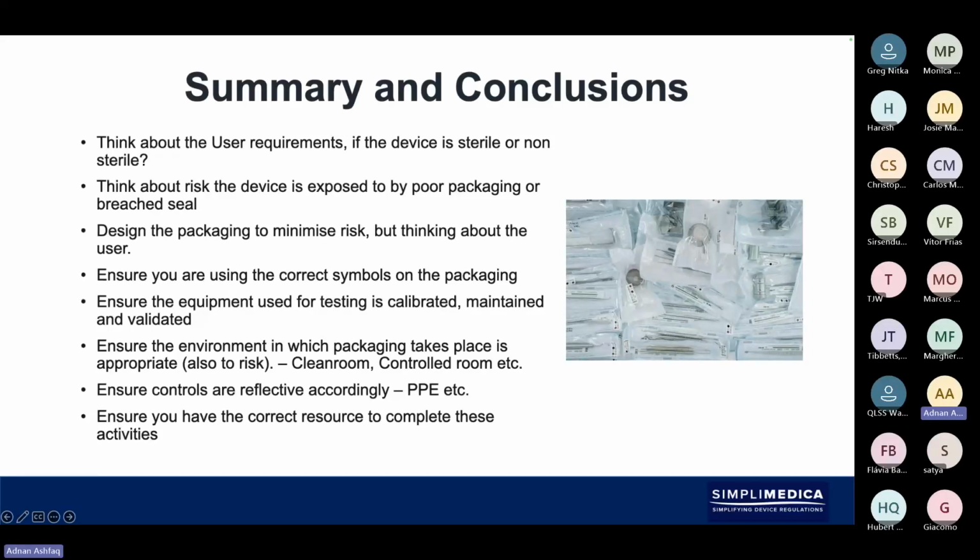Number one, is it mandatory to do packaging and transport validation for a non-sterile class 1 device per FDA, EU, SFDA? That's a good question. It's all very good practice to do this. Now, if it's a non-sterile class 1, according to these regulations, you may not be reviewed by a notified body on whether you're performing these activities or not, but it's definitely good practice to do that.